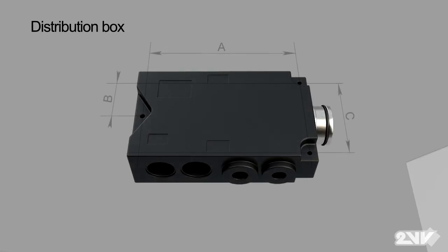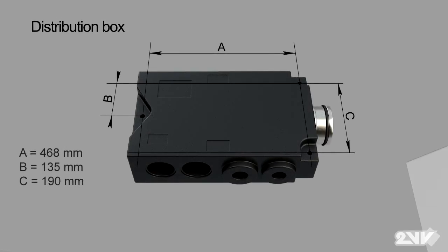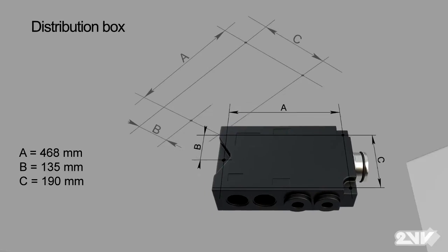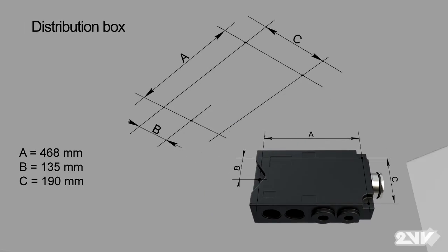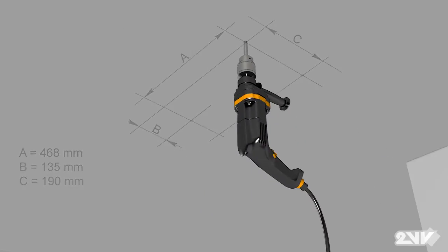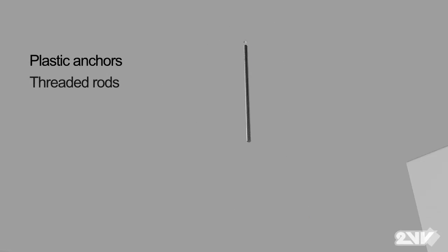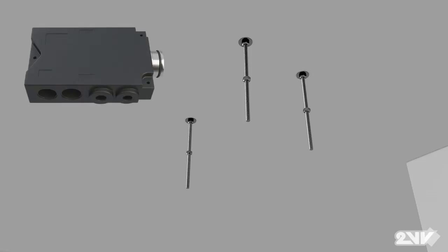First, you must set up the supply distribution box. Measuring the distance between the preset holes in the same way as the unit, mark 3 places on the ceiling that line up with the holes on the distribution box. Drill 3 holes. You will need anchors, threaded rods, washers, counter nuts and nuts. Now let's fasten the distribution box to the ceiling.